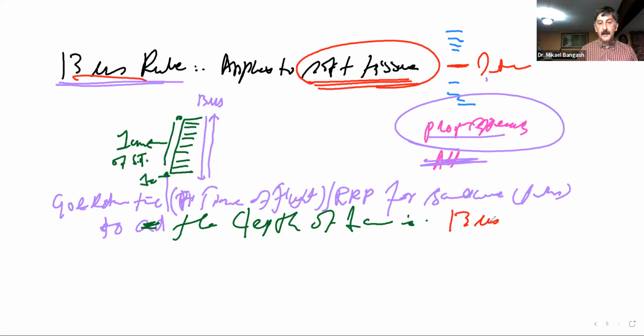How did they calculate that? Mainly because the speed of sound in soft tissue is 1,540 meters per second, or as they may say, 1.54 millimeters per microsecond. So based on this speed, that's why it is said that it's going to take the sound wave 13 microseconds to travel to the depth of 1 centimeter and go back.